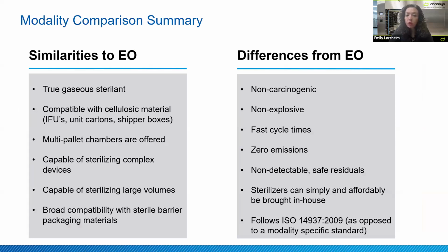Now we're going to go over a few brief summaries. There are similarities to ethylene oxide. Both are true gaseous sterilants. They're compatible with cellulose materials. Again, not all sterilization modalities are. Multi-pallet chambers are offered, so the scale-up process is very easy with chlorine dioxide. We can do complex devices. Also, again, large volumes, and we have broad compatibility with sterile barrier packaging materials.